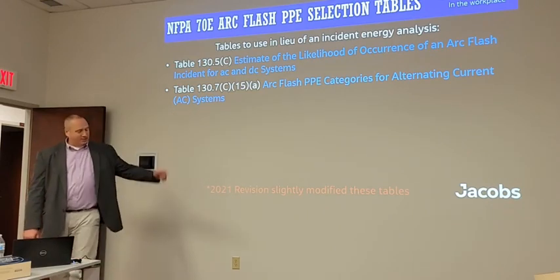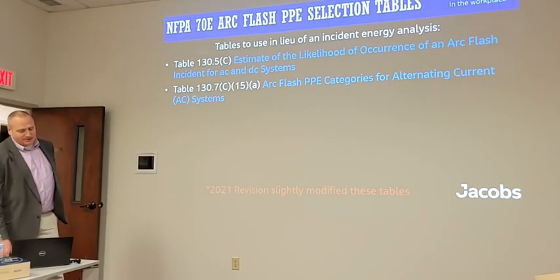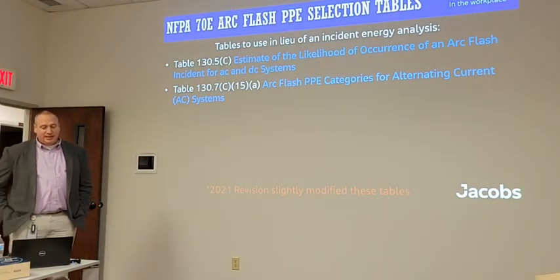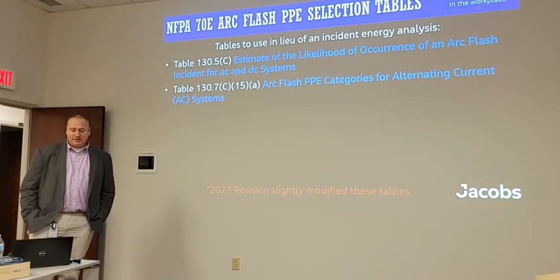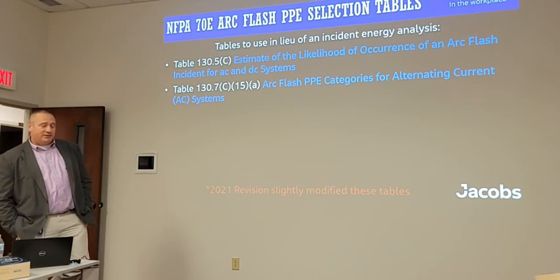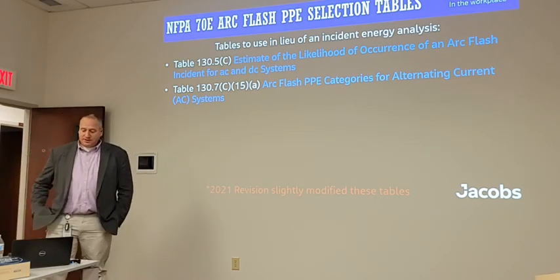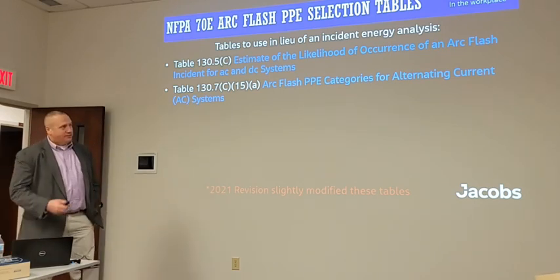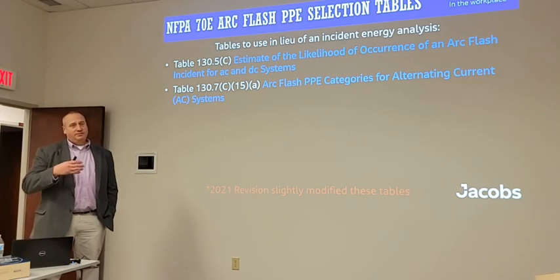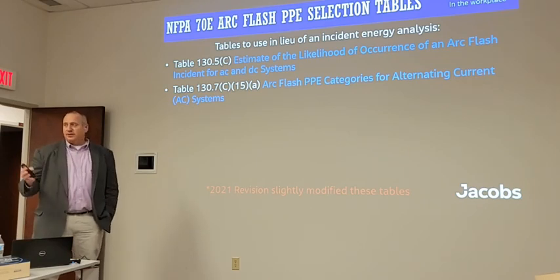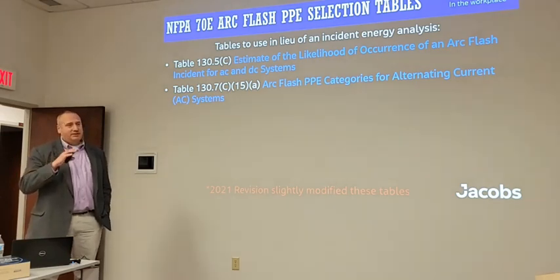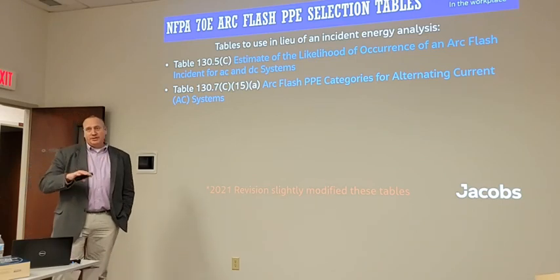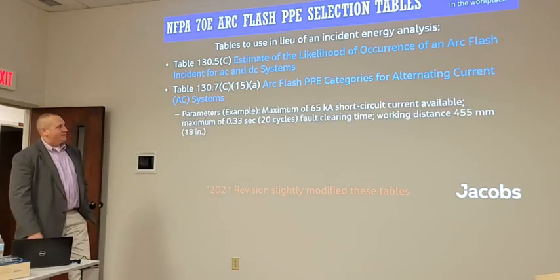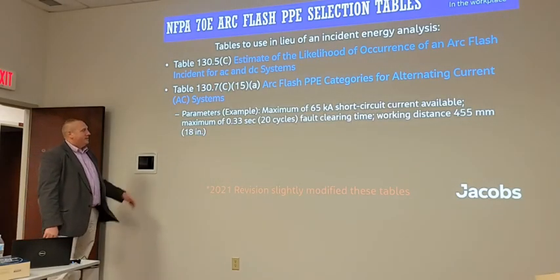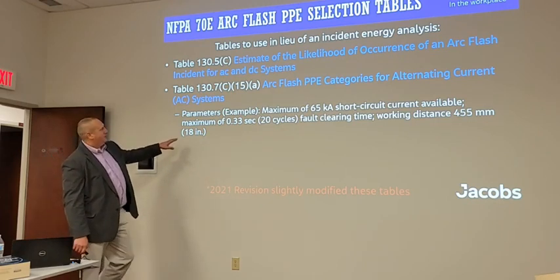This one is specifically for AC systems. There's another table, B, little letter B, for the DC systems. But this gives you categories of equipment: 480 volt panel, medium voltage switchgear. There's several different scenarios. And based on that type of equipment and some parameters, it gives you an arc flash PPE level. And this is an example of the parameter for one of the scenarios.